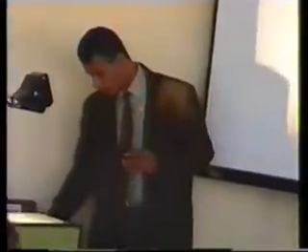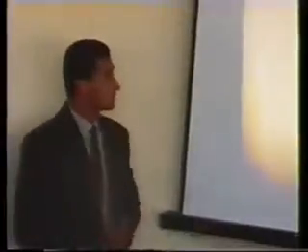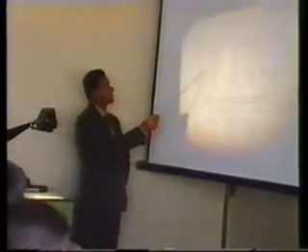Once we have obtained it, here we have some equations that we have computed, then we inputted the matrix A using the software package MATLAB, and we found the eigenvalues to be as follows, where we have considered 4 cases. In the first case, we took machine 1 as being represented by the classical model and the rest by the non-classical model. Then the system was found to be stable because the real parts of the poles that describe the system, which decide about its stability, were all negative.